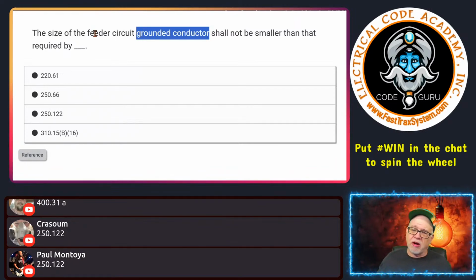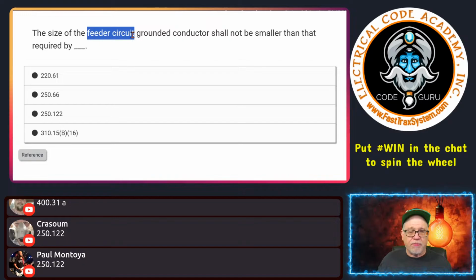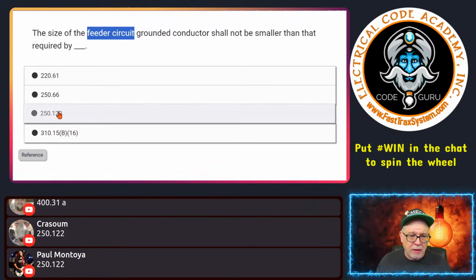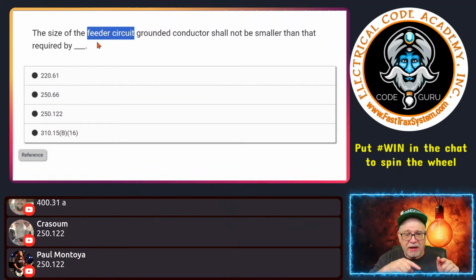So how do I get started in this journey? Well, it's a feeder, so for me it's going to be making a reference out of 215. I want to go look at 215 and bold scan rather than go back and look at feeder, because chances are under feeders in the back of the index, it's not going to have a structure that says feeder circuit and then grounded conductor. It might say minimum size or something. I know 215 is not big, and I'm not immediately going to jump to any of these answers because I need direction to get there. What tells me to go there? Maybe you already know the answer, but I need to know how to get there.